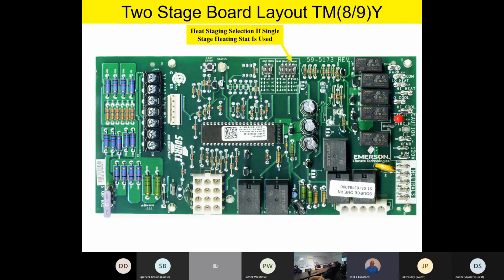There's an auto position as well. If the left dip switch is down and the right dip switch is up, as you take a look at the little screen print there on the board, if it's in the auto position, and we have a single stage thermostat input on W/W1, what's going to happen is the board will start looking at thermostat activity. In other words, how long it takes to satisfy from the last couple or three calls. It'll look at how long it takes to satisfy the thermostat as far as time is concerned. And it will then start making intelligent decisions.